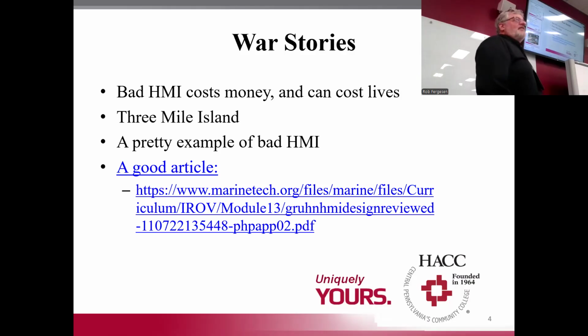In the case of a factory I was in, we had an operator who walked off and left a programmer working in the facility. That programmer figured the plant was empty, so he could run through some simulations. So he started running through simulations, but he did not observe his HMI properly and didn't realize his simulations were live in the plant.